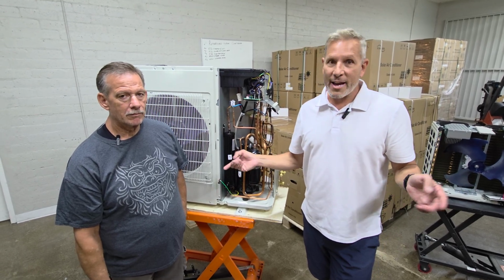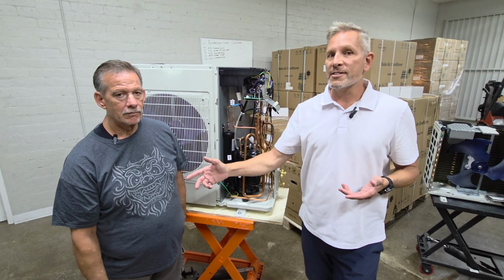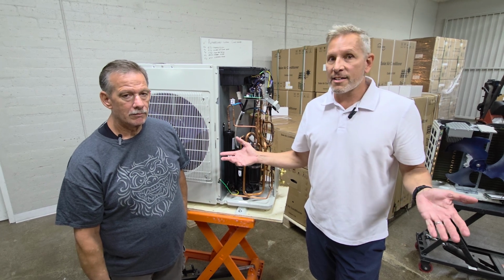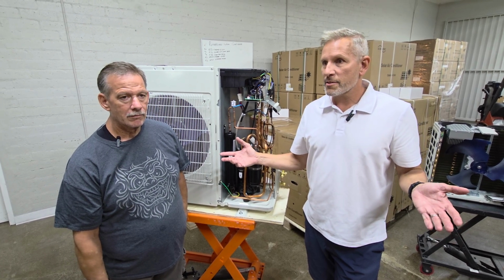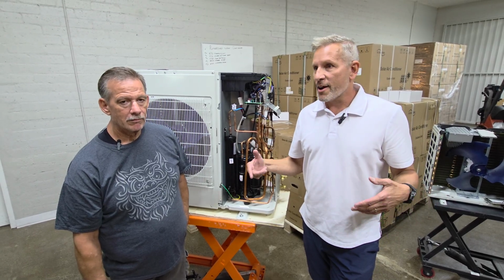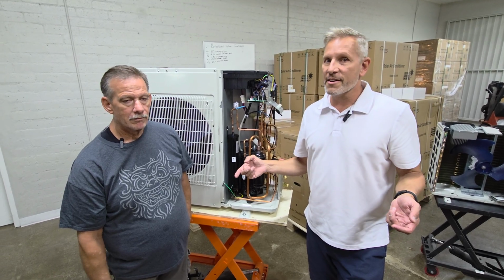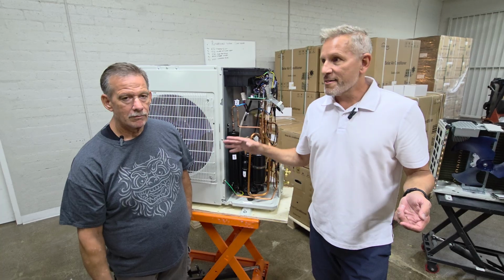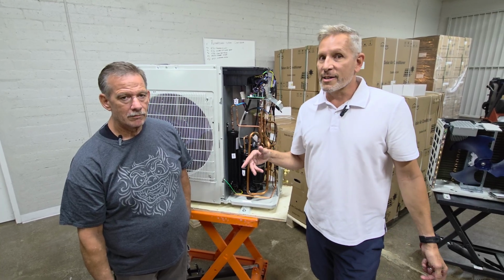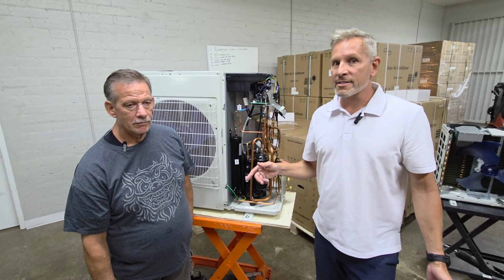Heat pumps used to be okay, we could heat down to like 35, 40 degrees. But after that, we certainly had to have supplemental heating. That's changed in the last couple of years with inverter compressors. Our inverter compressor unit could get down to around 15 degrees. And now this year, 2025, our R32 refrigerant gets down to 5 degrees. But this EVI is a whole new thing, going from 5 to minus 22. If my math is right, that's a 27-degree jump in extra heating capacity, okay?